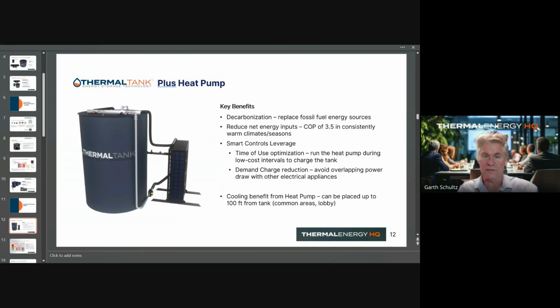What you benefit from using a heat pump and thermal storage is that you can run the system when those demand charges are not going to appear in the system. And additionally, being a device that takes 1 watt of electricity and turns it into 3.5 or 4 parts worth of thermal energy, you've reduced that overall demand in your load if you came from just resistive electric heaters. So we essentially have a triple economic benefit here.